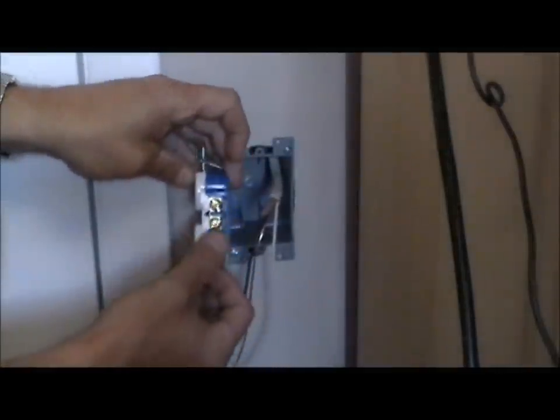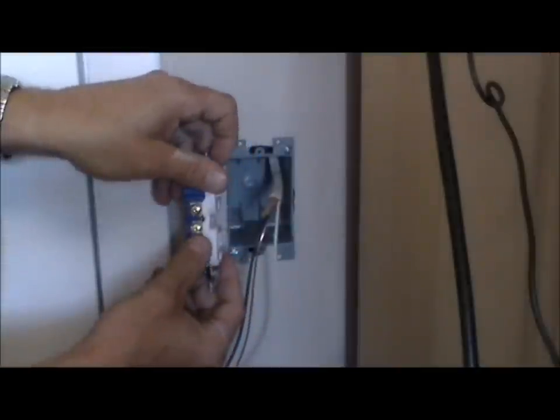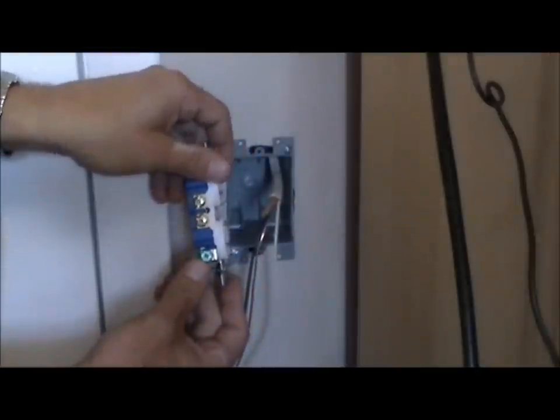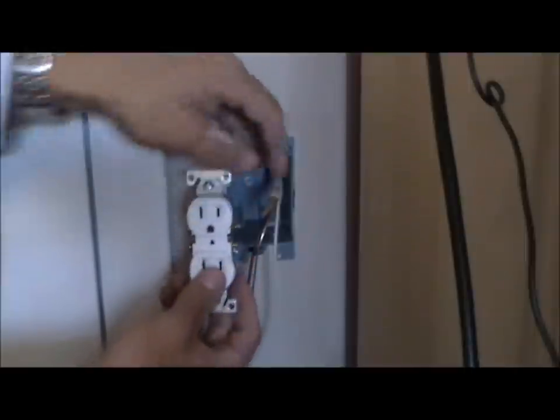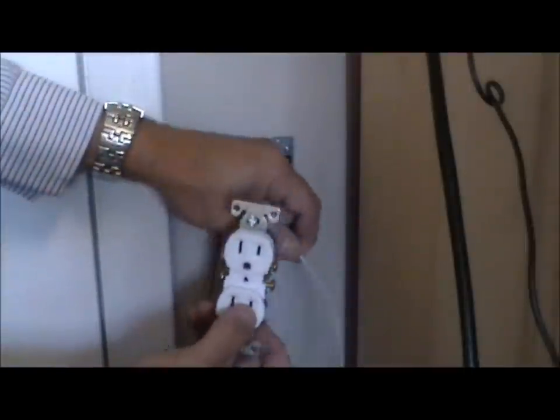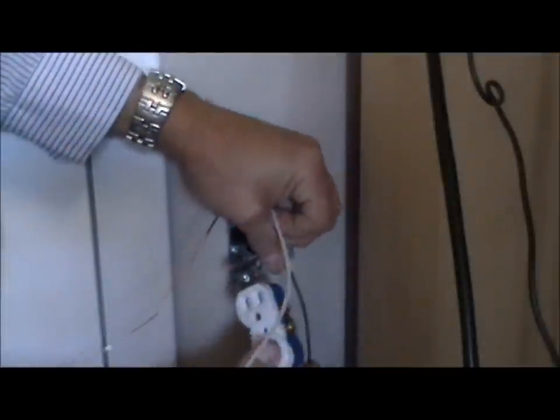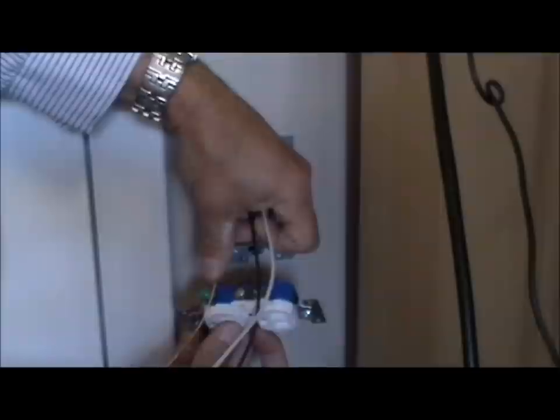We're going to install this 15 amp outlet. You'll see you have a gold side, a silver side, and a green ground screw. Now what you want to do is the white goes to silver, black goes to gold, and green goes to ground.